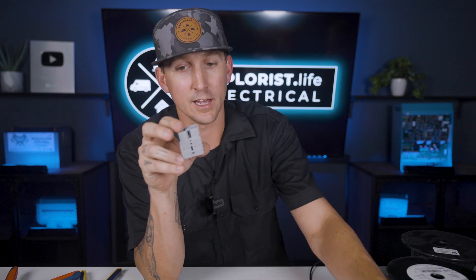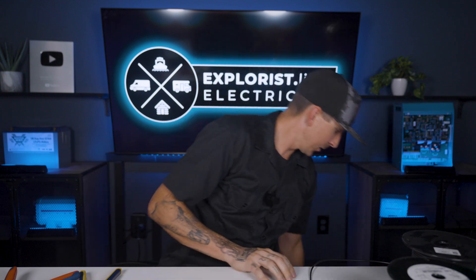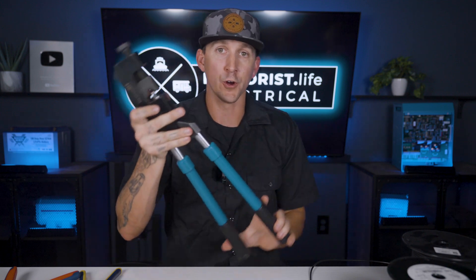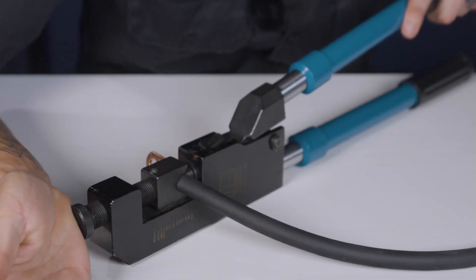Crimping Anderson connectors larger than 10 gauge — like 6 gauge or big 4/0 lugs — is the exact same process, just using a different crimper. The crimper I like for that is the battery lug crimper from Temco. If you need a refresher on how this crimper works, review lesson 4.05 of this academy, where we covered how to crimp wire lugs.